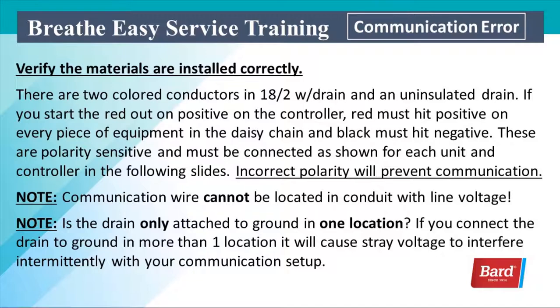There are two color-coded conductors in the 18/2 and an uninsulated drain. If you start out with red on positive at the controller, red must hit positive on every piece of equipment in the daisy chain, and black must hit negative. These are polarity-sensitive and must be connected as shown for each unit and controller. Incorrect polarity will prevent communication. Also note that communication wire cannot be located in the same conduit with line voltage, and the drain is only attached to ground in one location. Connecting the drain to ground in more than one location will cause stray voltage to interfere intermittently with your communication.